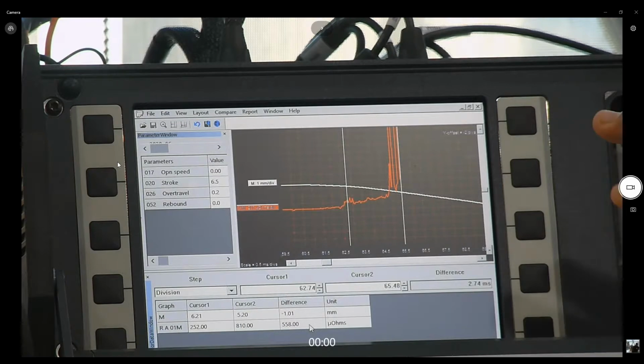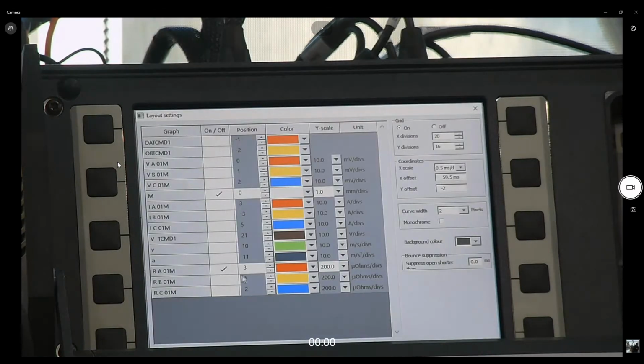Of course, I need to maybe adjust a little bit, but this is because of the air circuit breaker that we have here, and the motion is not proportional because I'm taking it from a different device. As I did for this phase, I can do for the other phases as well. I'll just note this value or write it down.